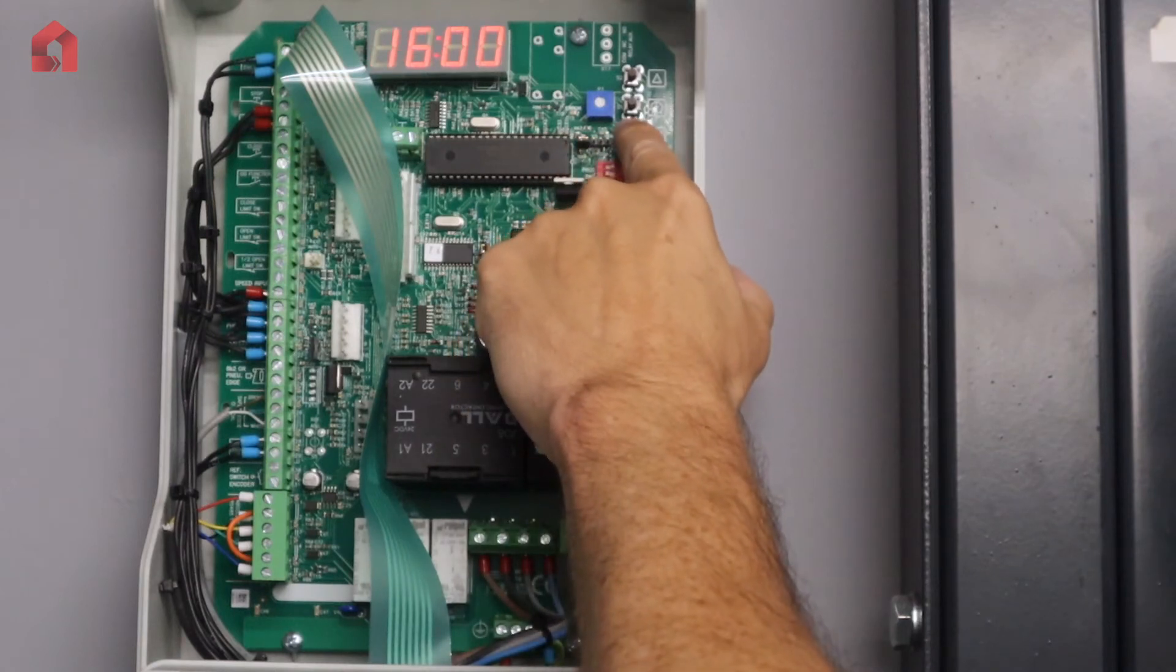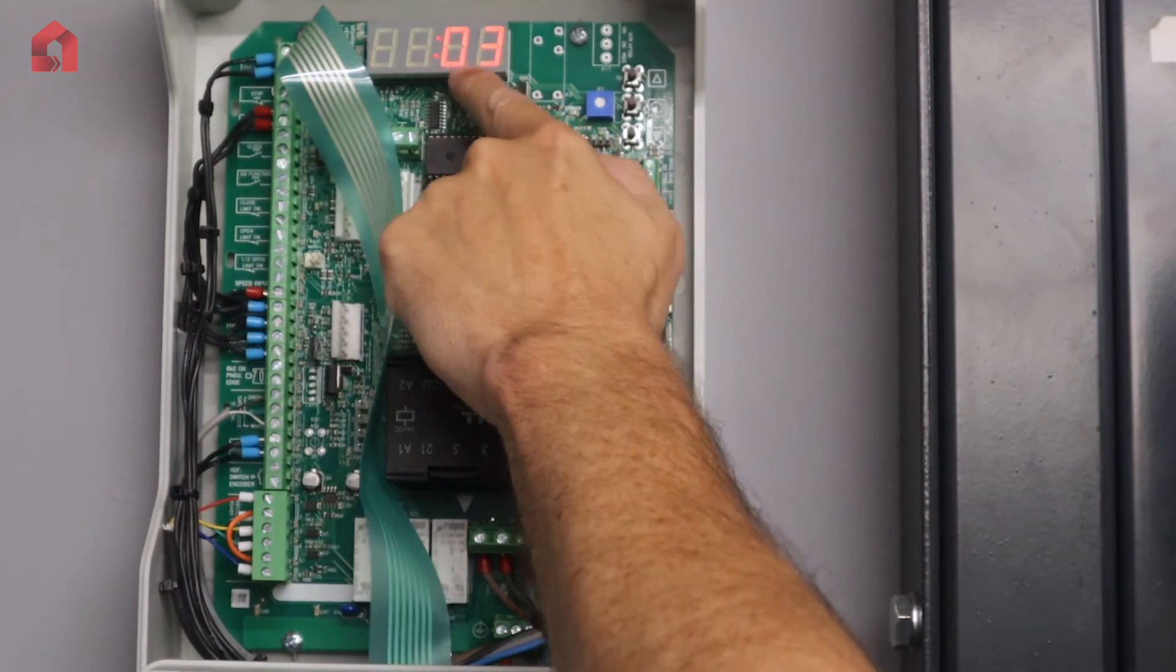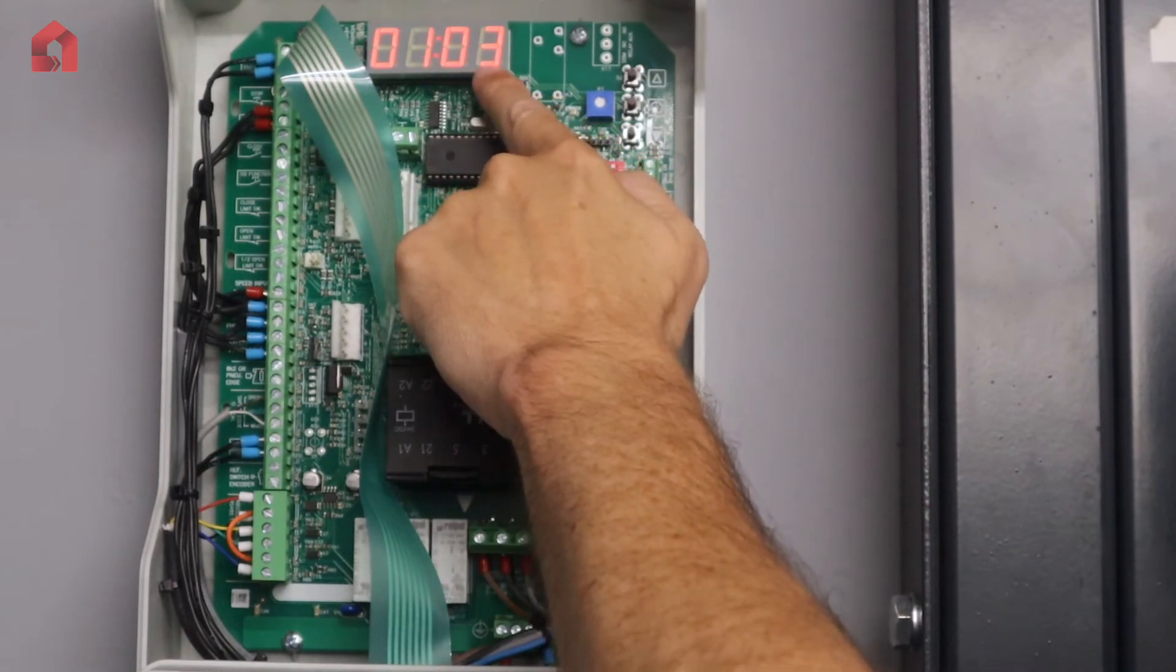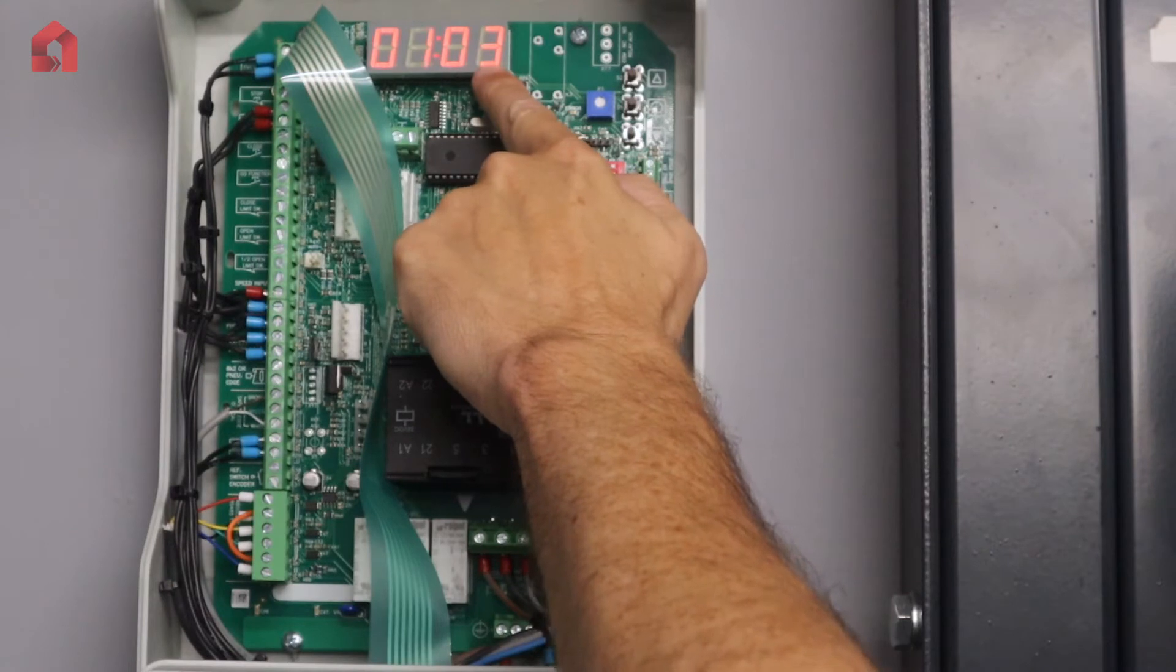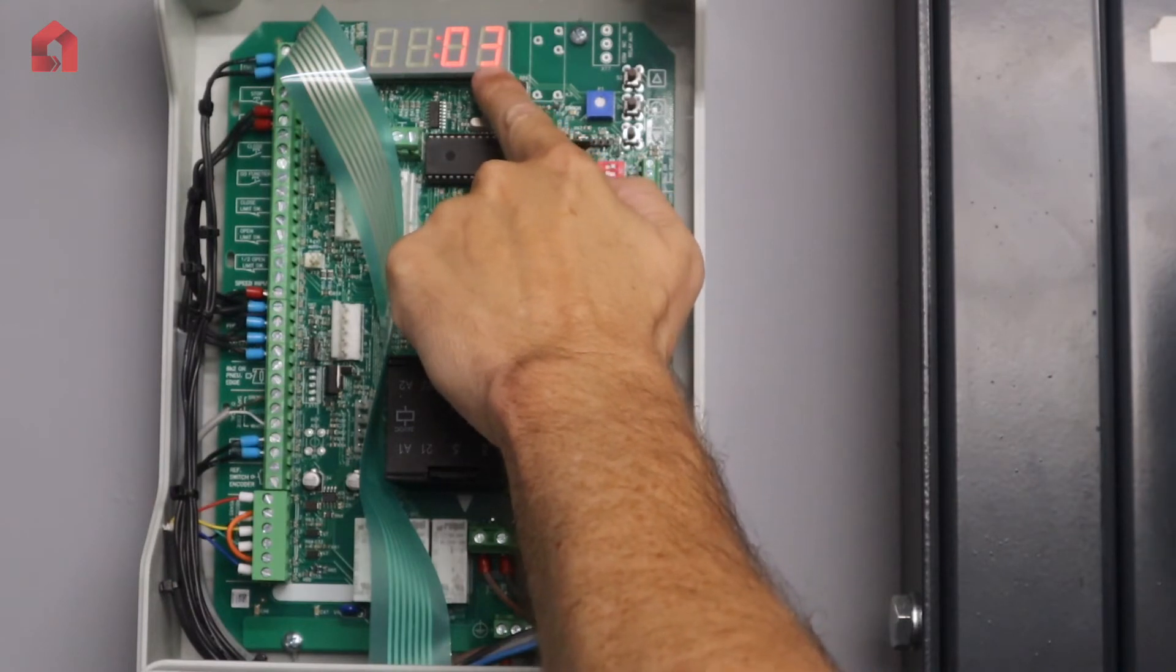So for example, if I go down to parameter 01, that is telling you how the door is running. So 03 is for impulse up and impulse down operation.